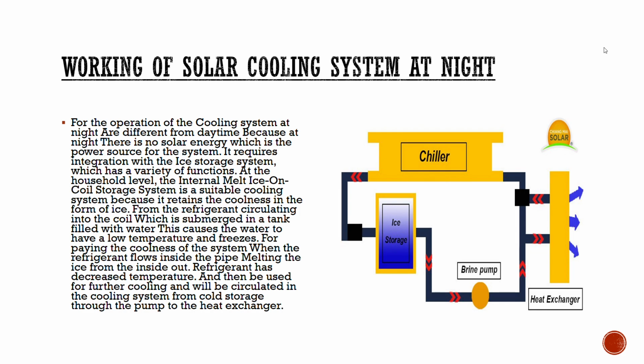The operation of the cooling system at night is different from the daytime because at night there is no solar energy, which is the power source of the system. It requires integration of a storage system which has a variety of functions at the household level. The internal melt ice on coil storage system is a suitable cooling system because it retains the coolness in the form of ice. The refrigerant circulates into the coil, which is submerged into the tank filled with water.